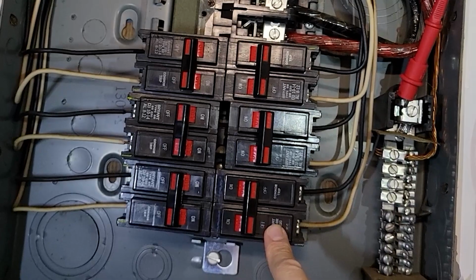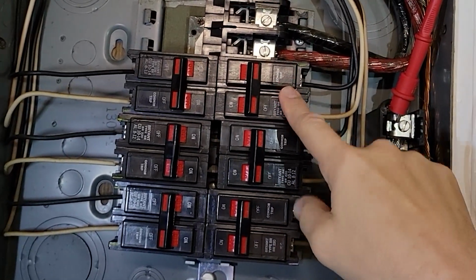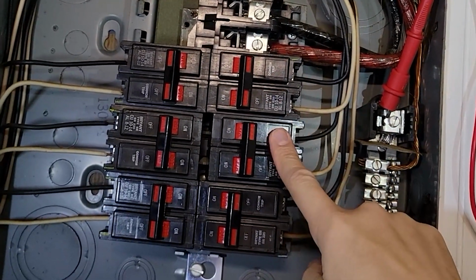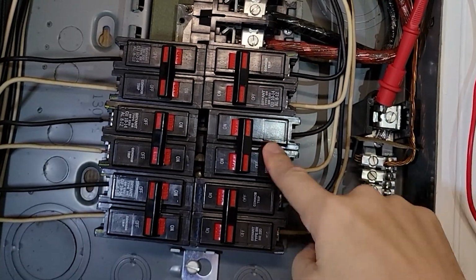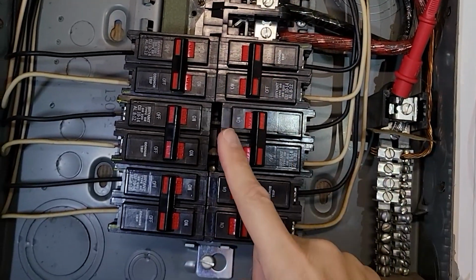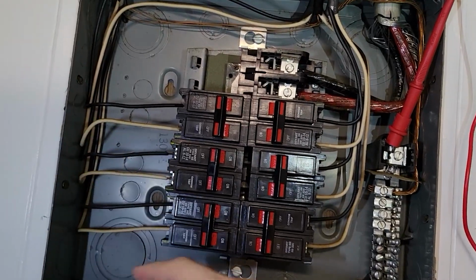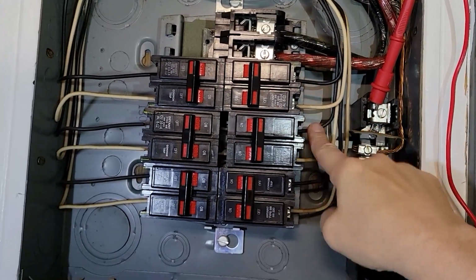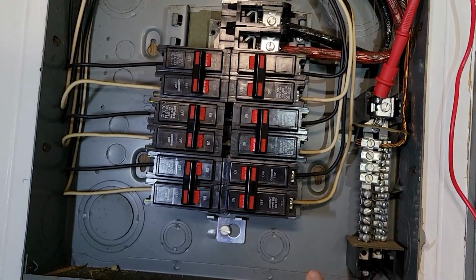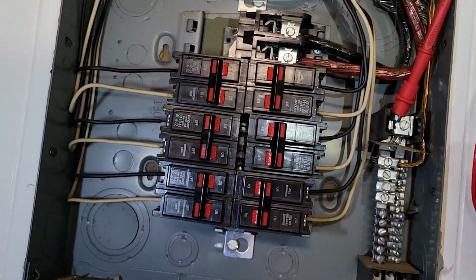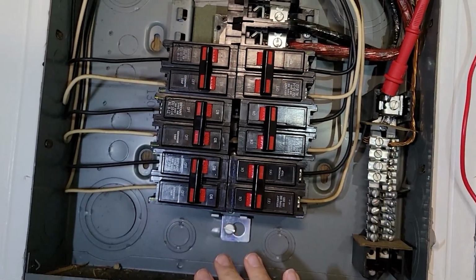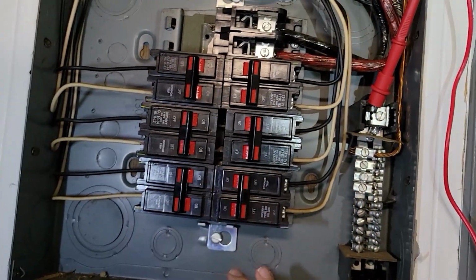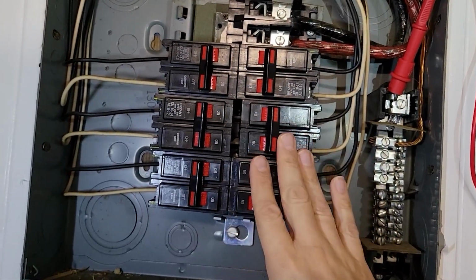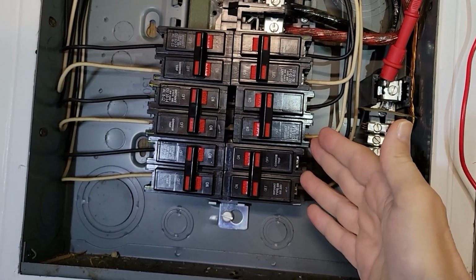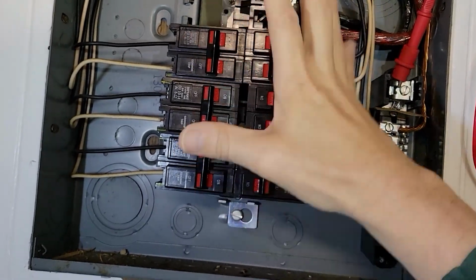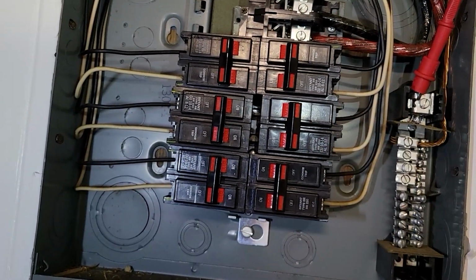These are all the 20 amp 240 circuit breakers that I'm going to leave in place except for one. I'm probably going to break out over on this side. More than likely, I will disconnect the wires so that when we activate the 100 amp circuit to this box, you can only trip one thing. If you turn something else on, nothing will happen because it'll be dead-ended here. So it's just a safety thing. I don't want these wires being fed.